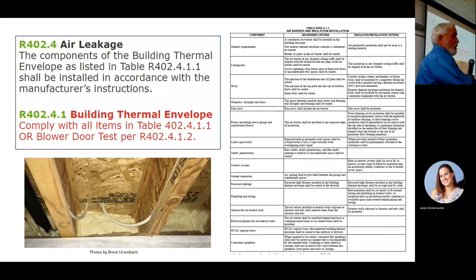First one, install the insulation per the manufacturer. Have a continuous air barrier. All the gaps and voids are sealed between conditioned and unconditioned space. Air permeable insulation not used for air sealing, so you don't use fiberglass or rock wool to stop air leakage. Closed cell foam is the only insulation that serves as an air barrier. Drop ceilings, soffits, shafts, chase shall be capped.